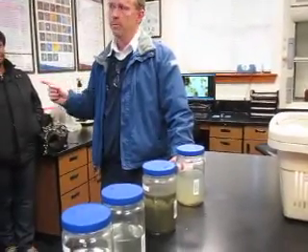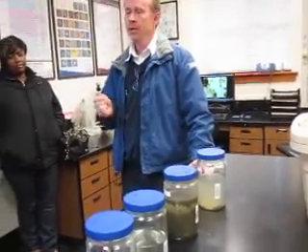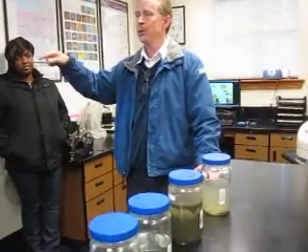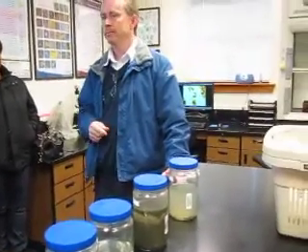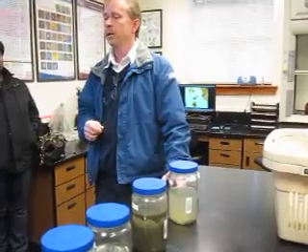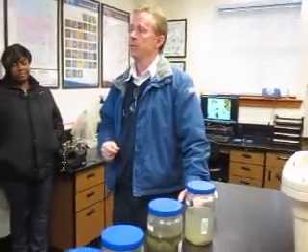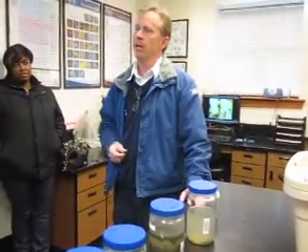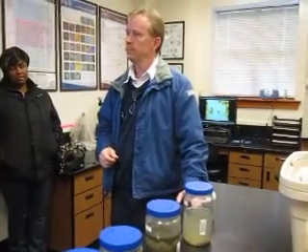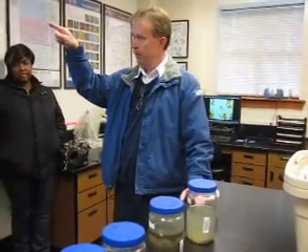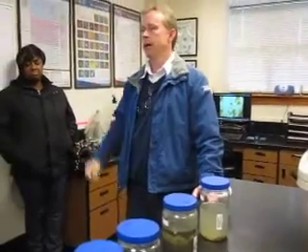That's to make it through all of our basins. How do you figure detention time? You've got to figure out the volume in each one of your tanks and what the flow rate is. And there's a formula that you work out that you can use to figure the detention time. Right now, with the flow coming in, I would say we're probably at 12 hours from front to end, coming in the front at preliminary treatment, flowing out the back.